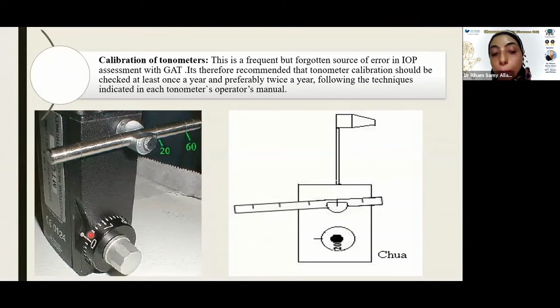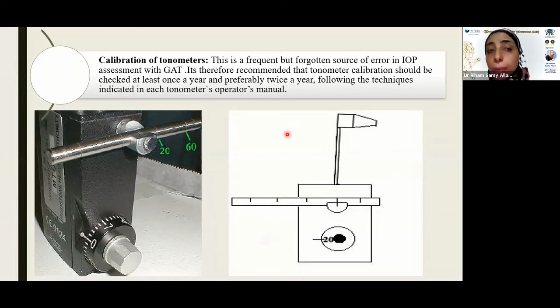This calibration bar, for example, is set at 0, 20, and 60. You put it at the 0 position and put the knob in the same position, and then the bar is straight and there is no movement on the applanation tip. When you rotate this knob 2 millimeters or 4 millimeters above and below this number, you see a movement or a twist or a spring in the applanation tonometer itself. If there is any error in calibration, it should be returned to the manufacturer for maintenance.